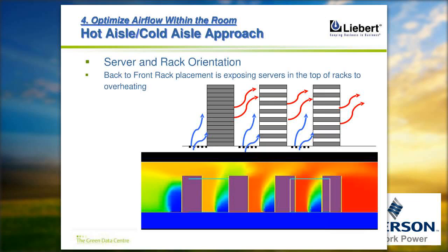We should strictly mention the hot and cold aisle approach. In India, there are quite a few data centers I have seen where the racks are installed back to front, which means the hot air of the front rack is going into the inlet of the server. That may impact the overall hygiene factor of the data center. So it is very important that we use server rack orientation properly.